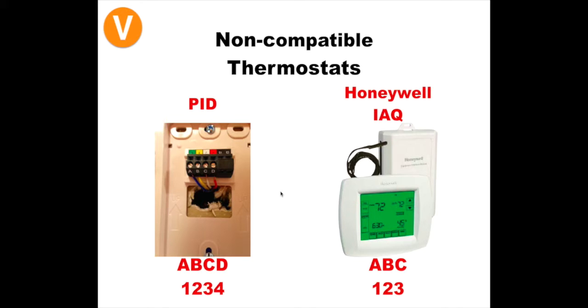So we want to make sure that we don't try to hook up to these. The reason some technicians do it is that instead of going off of the terminals like A, B, C, D, they look at the color of the wire, and if they think that the color of the wire actually matters, they would try to match up the green to G or the red to R. And in the HVAC industry, on the thermostat side of things, the color of the wire doesn't matter. So we want to make sure that we're going off of the terminals and not the wire color.